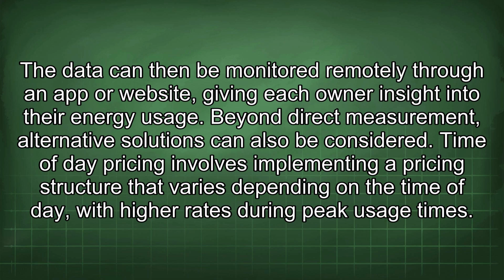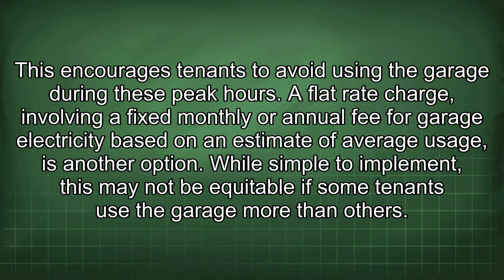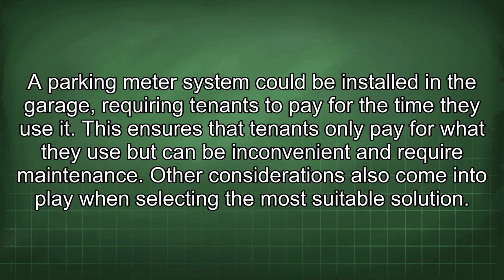Beyond direct measurement, alternative solutions can also be considered. Time-of-day pricing involves implementing a pricing structure that varies depending on the time of day, with higher rates during peak usage times. This encourages tenants to avoid using the garage during these peak hours. A flat rate charge, involving a fixed monthly or annual fee for garage electricity based on an estimate of average usage, is another option. While simple to implement, this may not be equitable if some tenants use the garage more than others. A parking meter system could be installed in the garage, requiring tenants to pay for the time they use it. This ensures that tenants only pay for what they use, but can be inconvenient and require maintenance.